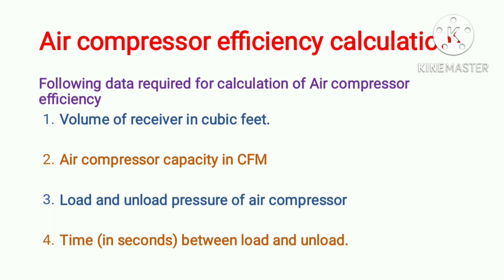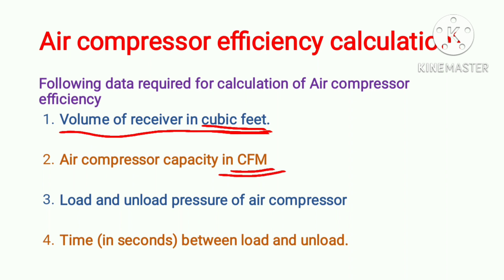The first parameters required for volumetric efficiency calculation of an air compressor are: volume of the air receiver in cubic feet — the receiver in which we store compressed air after compression. Then, air compressor capacity in CFM, which you will find on the nameplate of the air compressor — that is, the design capacity. Then, load and unload pressure of the air compressor.